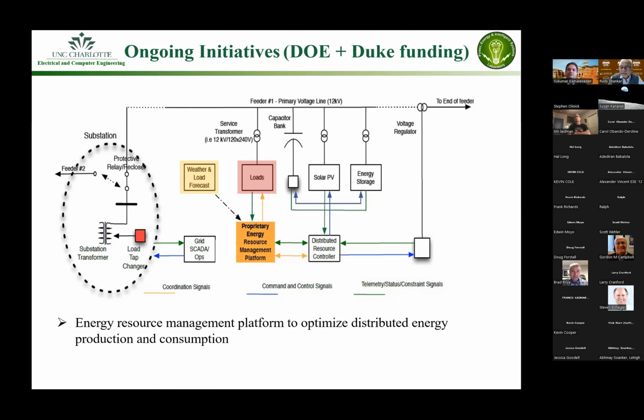The size of that PV farm will determine the size in kW for the battery. If we are using only capacity firming, not nighttime support as we were just discussing, it should be a 3-hour duration. So like a 250 kW with 750 kWh energy capability for a 1 megawatt PV, which is around 20-25%, a little low in my opinion, but 30-35% of the capacity of the photovoltaic is a good mix to do these functions, not the nighttime support.